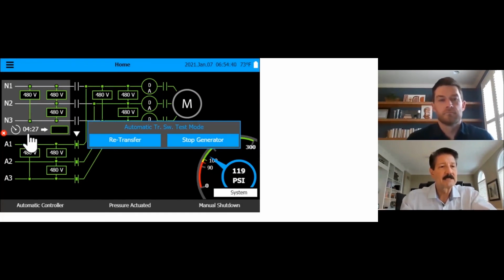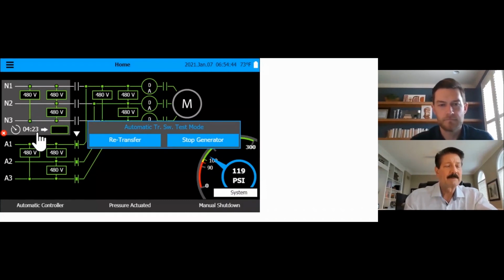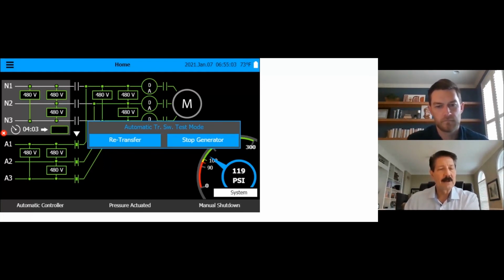And the way this is set up, we run this for 5 minutes. This is an adjustable timer here, but typically we have it factory set so that if normal power is maintained for a minimum of 5 minutes, it's showing stability. And part of this, before you transfer over, I'm doing a regular test here, a manual test. But in real life, if the voltage drops for a fraction of a second, there is a 1 to 3 second delay required by code that's adjustable before a signal will be sent out to the generator to start. And why did they do that? They don't want to have consistent voltage fluctuations that are going to cause nuisance starting on that genset. So that's why that delay's there, and it is field adjustable. Typically 1 to 3 seconds is what it's set up for.